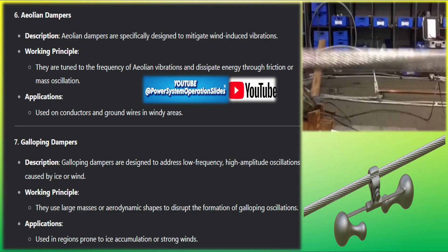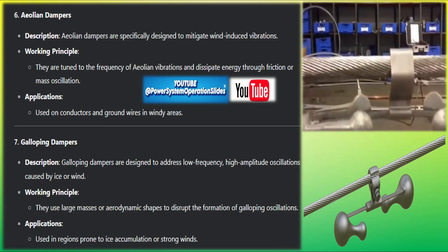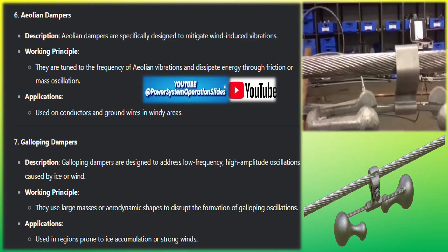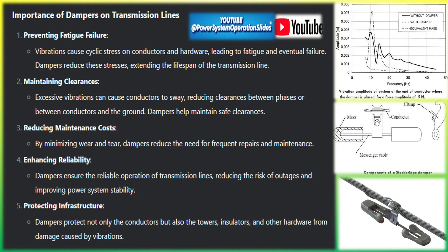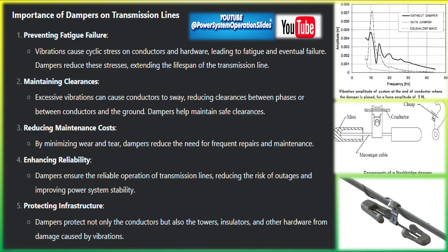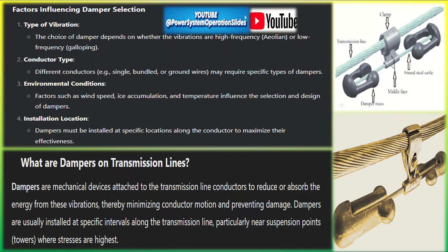Dampers are mechanical devices attached to the transmission line conductors to reduce or absorb the energy from these vibrations, thereby minimizing conductor motion and preventing damage. They are usually installed at specific intervals along the transmission line, particularly near suspension points and towers where stresses are highest. Dampers work by absorbing the mechanical energy of the vibrating conductor and dissipating it as heat or redirecting it into the mass of the damper.